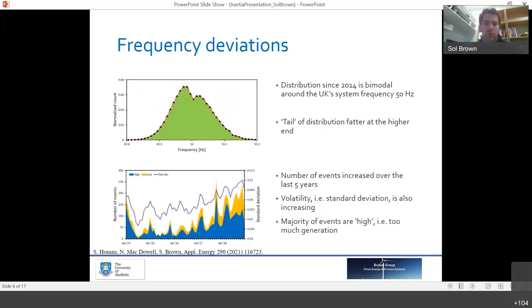And if we dig into what's happening with the frequency deviations, within the current and the past few years, you can see that if we plot deviations as a distribution, it's a bit bimodal around the 50 hertz point that we want to operate at. It's slightly high. You get slightly more lower frequencies, so we see drops a little bit more than we see increases. And the tail of the distribution is a bit fatter at the higher end, so where we have high events. We'll come back to that in a bit.